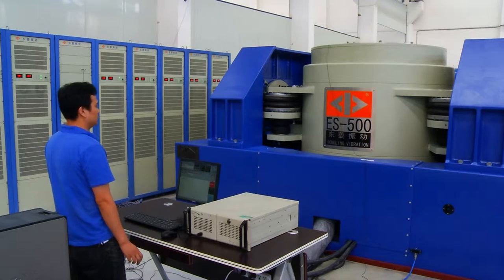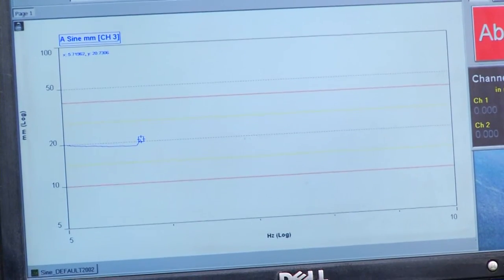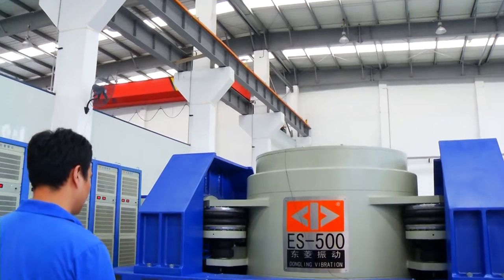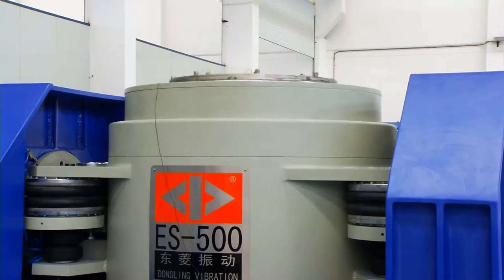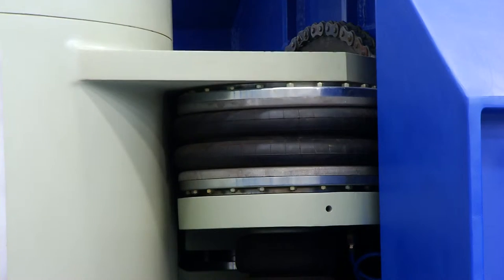The system's rated sine and random force is 500 kN, which is the world's largest. Usable frequency for sine is 1500 Hz and for random is 2000 Hz. The maximum payload is 15,000 kg.